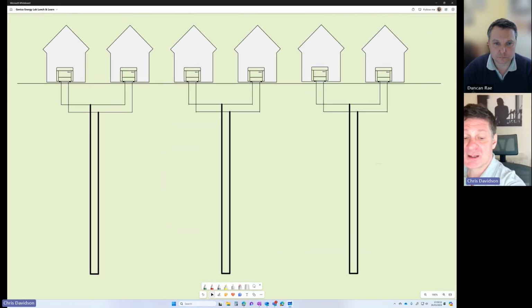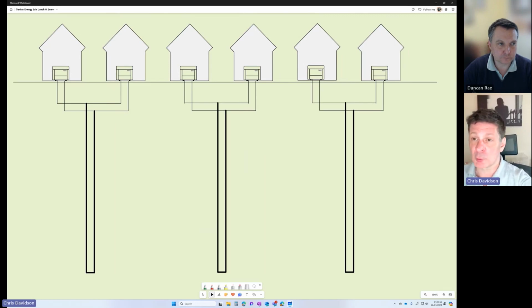We could take the opposite view and break this heat network up. Here's an extreme example where we've got one borehole between two dwellings. Obviously we can't take the same level of diversity in these networks. If you're not familiar with diversity, have a look on Wikipedia. There are some good definitions, although the definitions of diversity in ground loops aren't that well put out there. We've got definitions internally that we use. Let's break this network up, two dwellings per borehole.